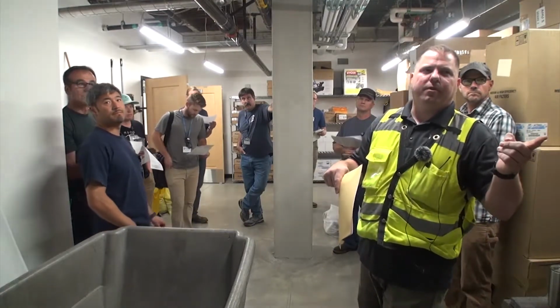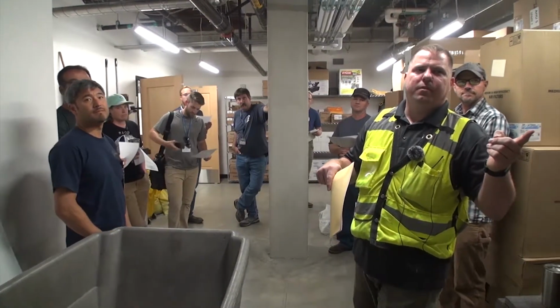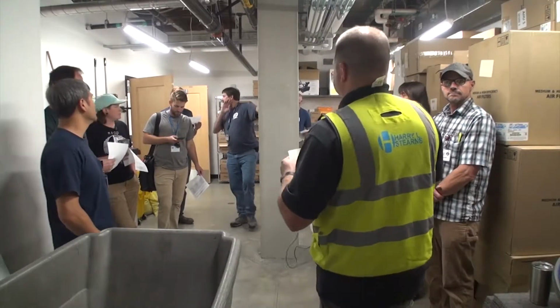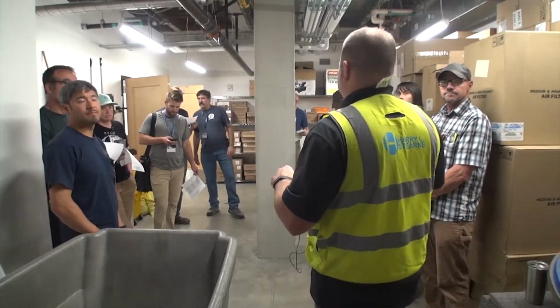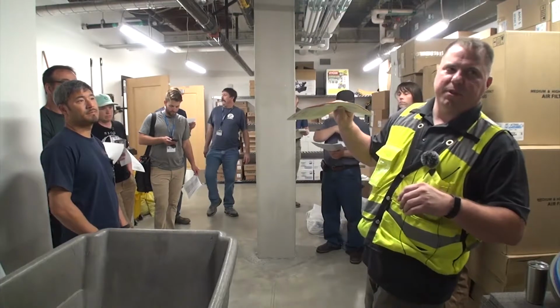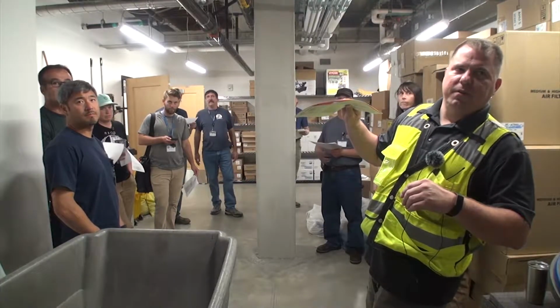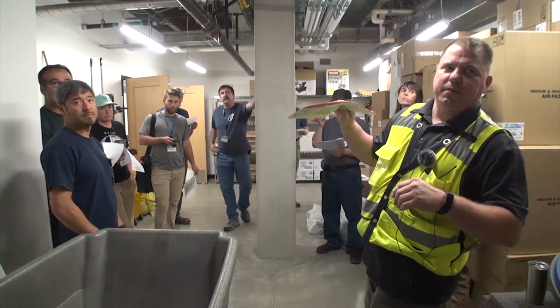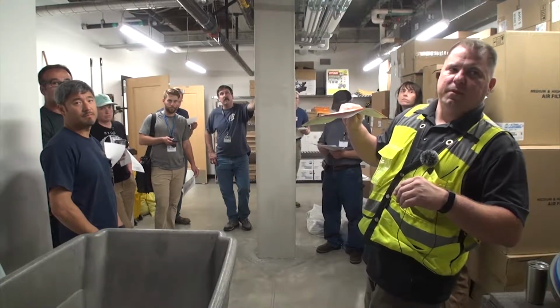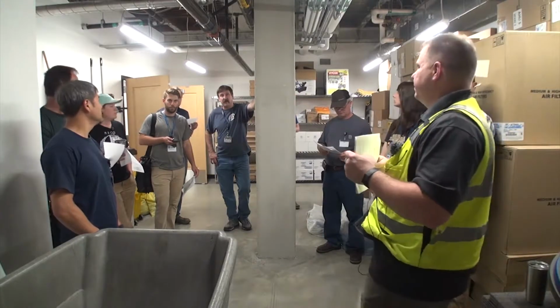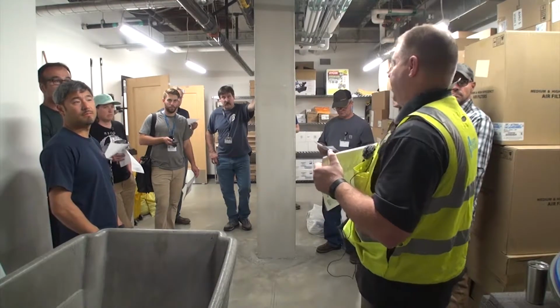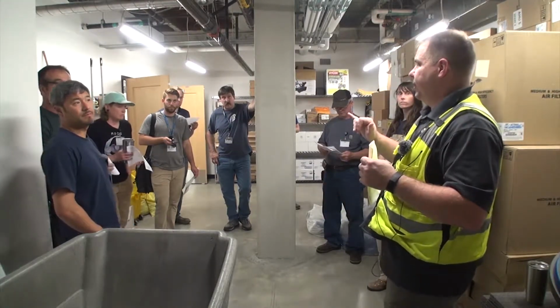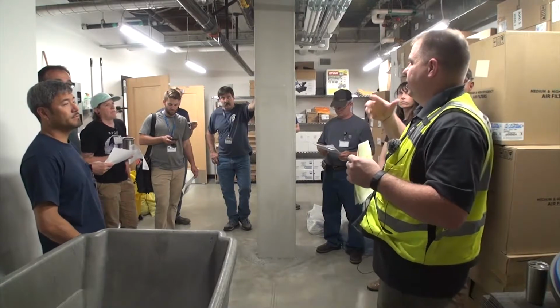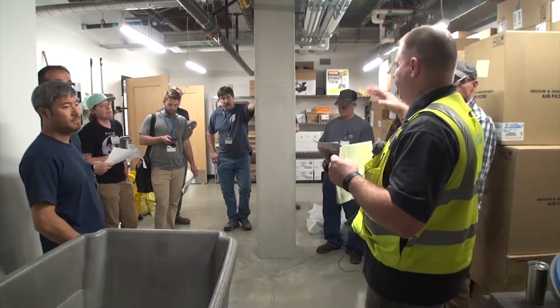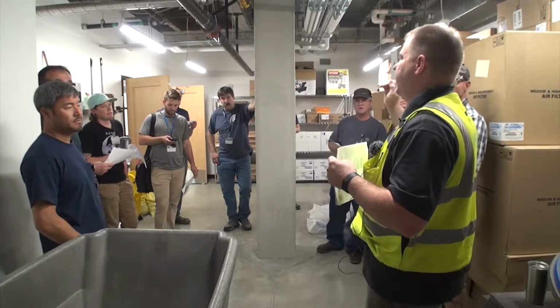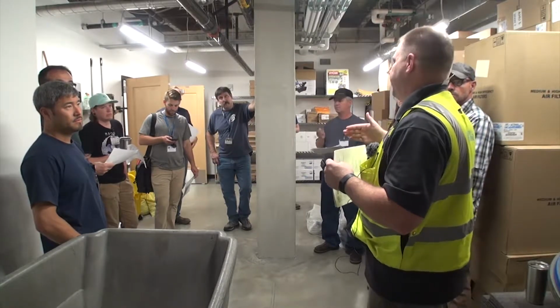What's the time clock for the hallways? I believe it's 6 to 6 at the moment. So at 6 a.m. the hallway lights go to 25%. Halls go to 50% when unoccupied during the day, and 100% when occupied. At 6 o'clock, do they switch off completely? No, what they do is change behavior. At 6 o'clock the system still works on the occupancy sensor, so if it's occupied it'll be at 100%, and when unoccupied it'll be 0 instead of 50%, so it'll be off.